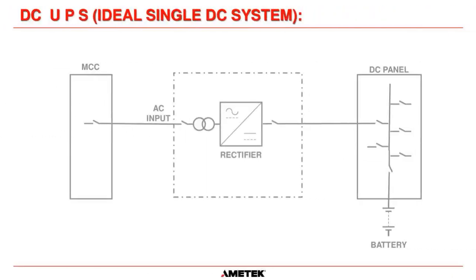Now, this is what most people would see as the standard single charger DC system that is out there. Okay, so you will have 480 volts being fed from your MCC, whether it's your emergency board or a normal board, from a bucket there, and then that will go to our charger terminals. And then inside the charger, you will have an AC input breaker. And as I said before, you will have this transformer, and then the rectifier will convert the AC into DC. And then on the charger itself, we will usually have a DC output breaker. And then the cables from the charger go to a DC panel.